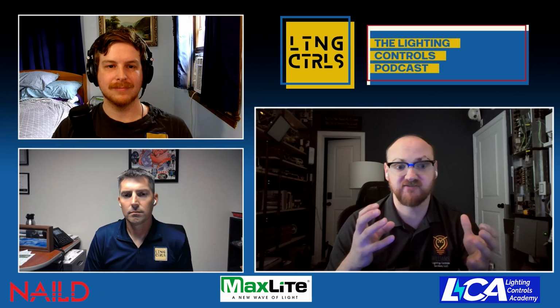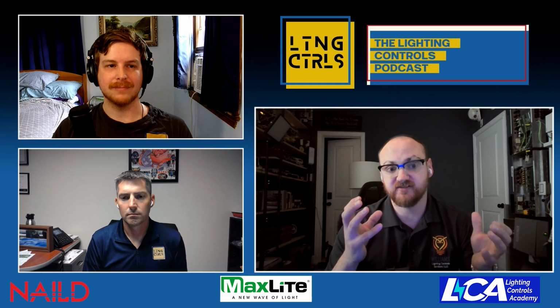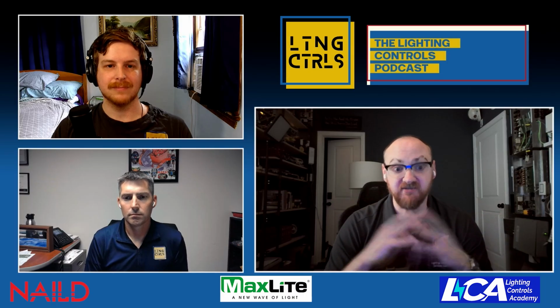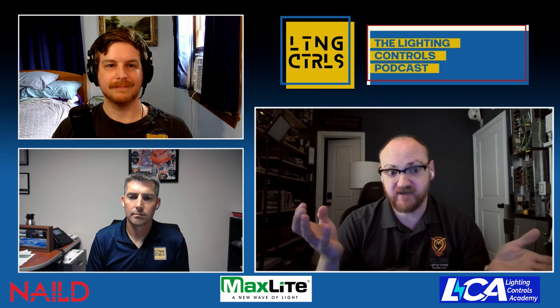And that's going to be a warranty issue, because let's face it, manufacturers for the most part train technicians to cover about 10% of sensors. They don't tell us to check every single sensor because one, we don't have time, and two, on a construction site or occupied space, I'm only paid for 8 hours by the manufacturer. My time is there when the electrician is there, because I need the electrician to fix issues I find, not to go back and troubleshoot every occupancy sensor on my own time. That's the role of the commissioning provider.